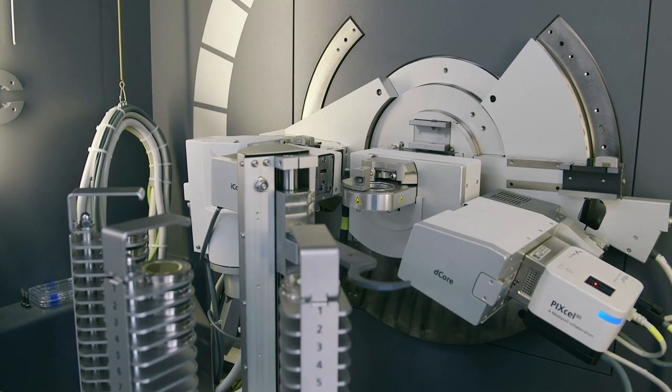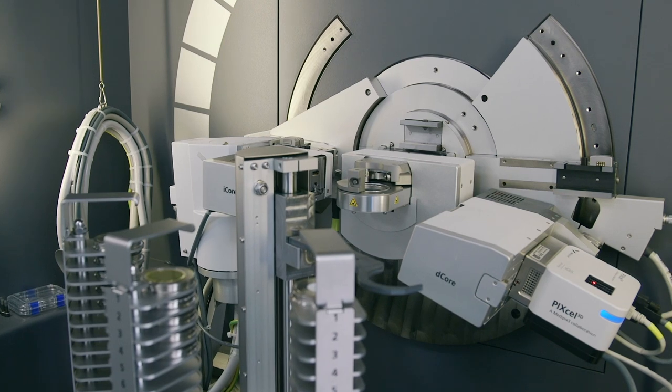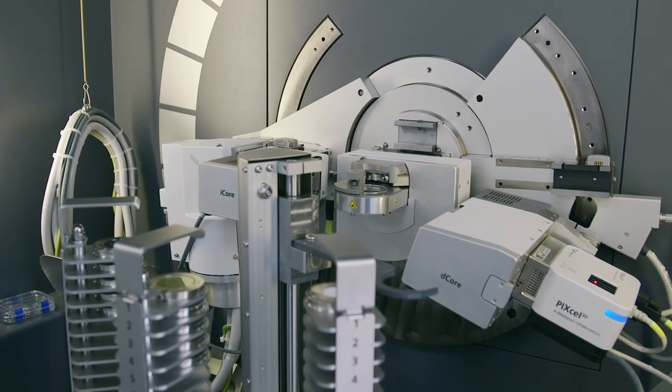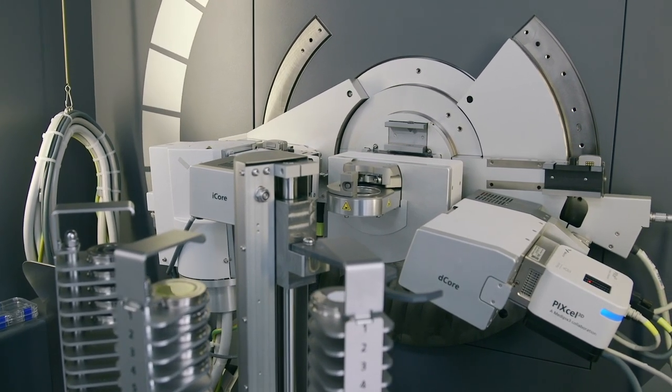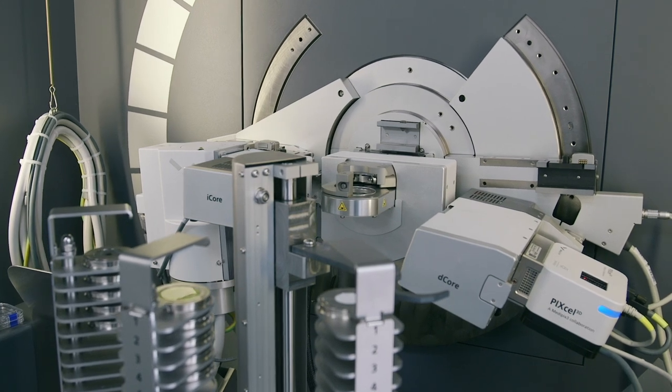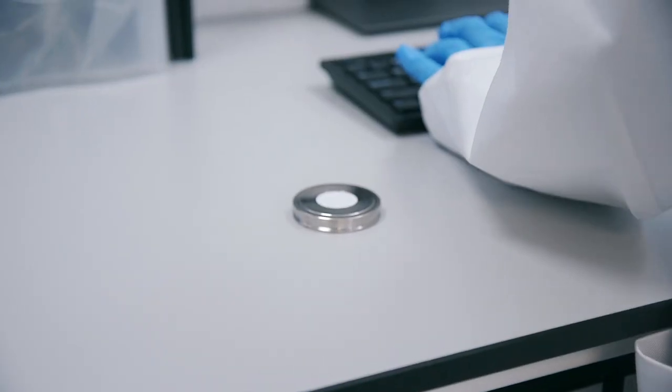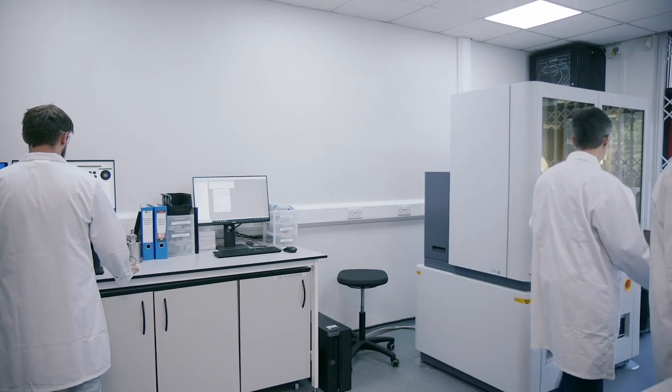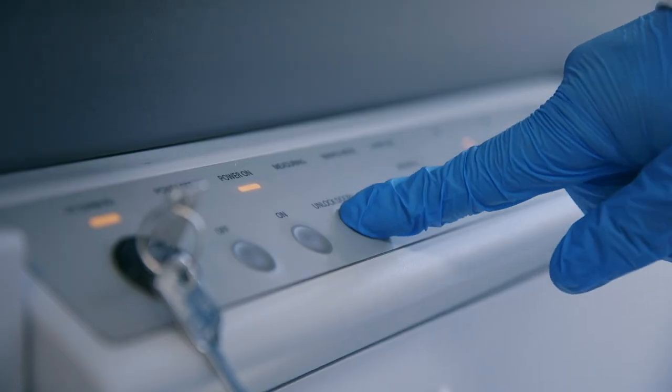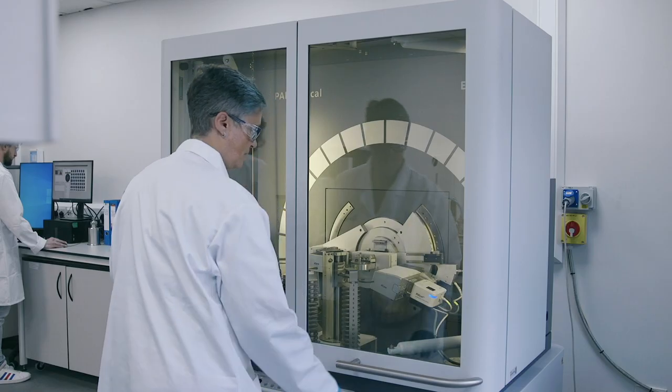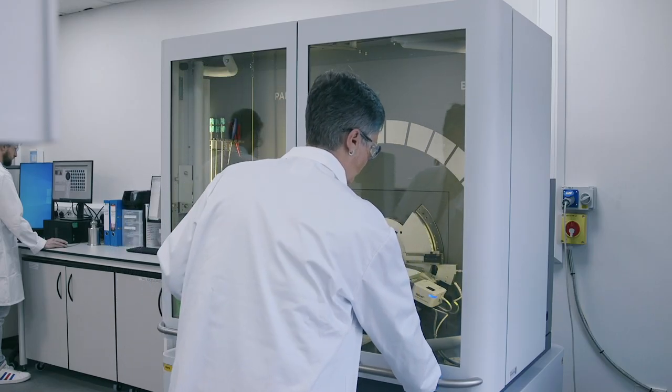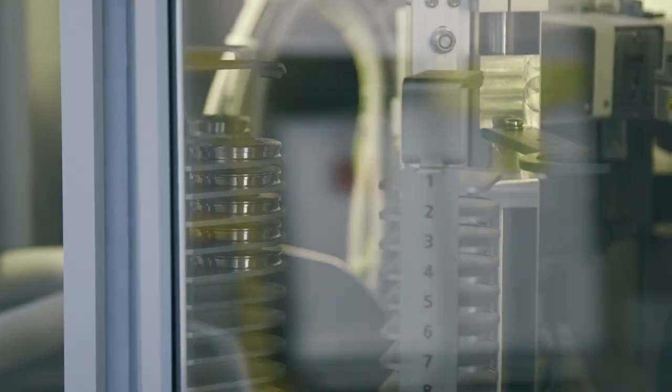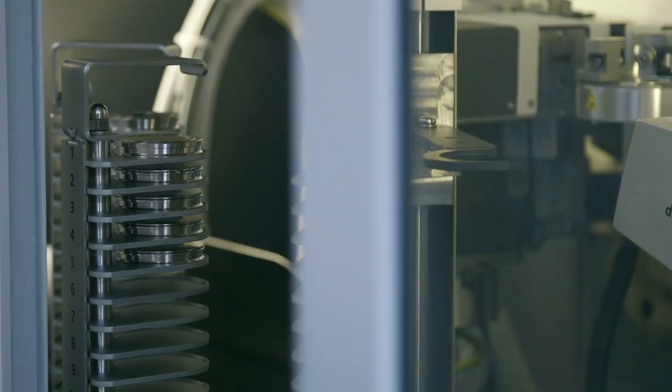Our state-of-the-art Malvern Panalytical Empyrean X-ray diffractometer allows us to measure powders, films, and solids for crystallinity, amorphicity, physical impurities, phase content, chemical identification, and many more physical properties. We use both reflection and transmission modes with a high-throughput stage for multi-well plates and an environmental stage for assessing the impact of temperature and humidity on a sample's solid form.